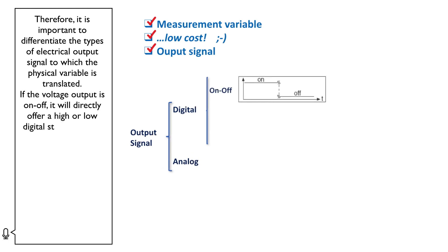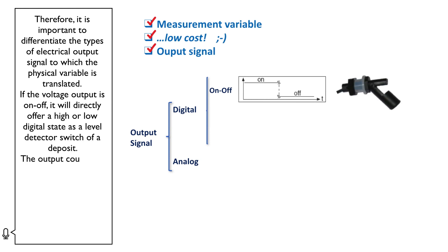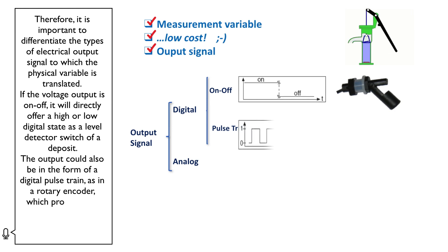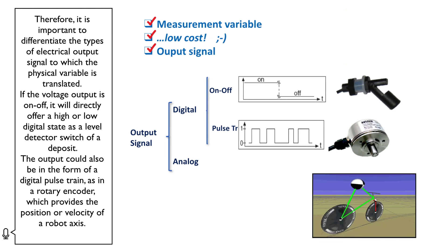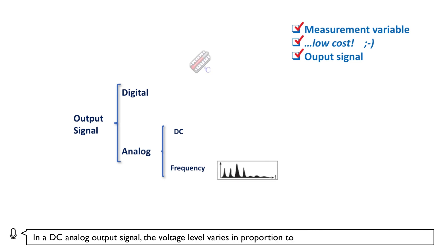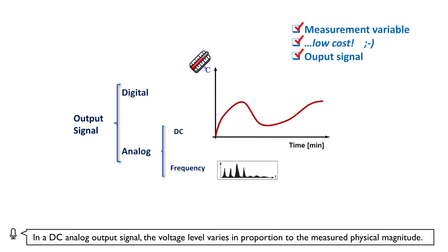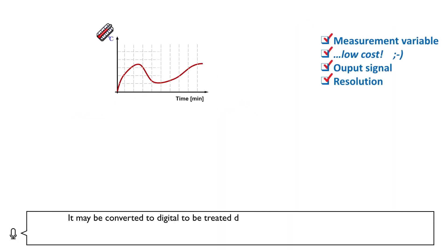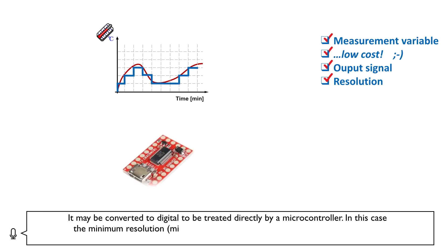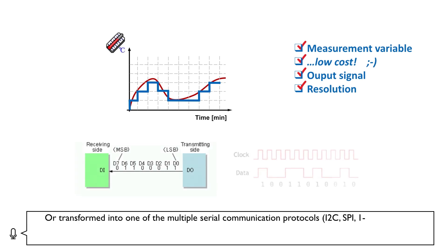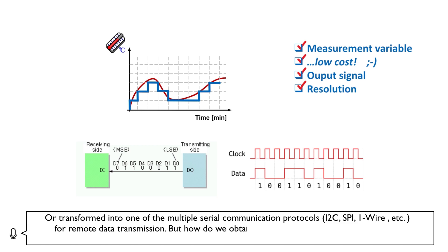If the voltage output is on-off, it will directly offer a high or low digital state, as in a level detector switch of a deposit. The output could also be in the form of a digital pulse train, as in a rotary encoder which provides the position or velocity of a robot axis. In a DC analogue output signal, the voltage level varies in proportion to the measured physical magnitude. It may be converted to digital for a microcontroller, where minimum resolution should be taken into account, or transformed into one of the many serial communication protocols — I2C, SPI, one-wire, etc. — for remote data transmission.